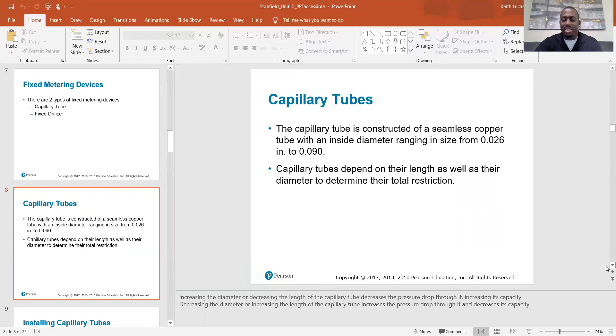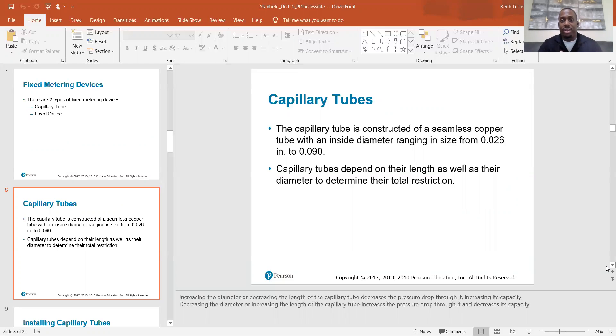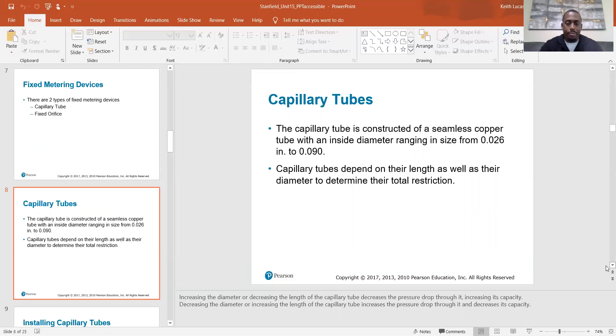Every time I've changed a metering device, I replaced the defective one with a new one of the exact same type. I've never swapped from a capillary tube to a TXV. I tend to stick with the manufacturer specifications, because the last thing I need is to spend all my time diagnosing a problem, fix it, and then create new problems in the future by improvising rather than following manufacturer specs. Every time I replace a metering device, I replace it with the exact same type.